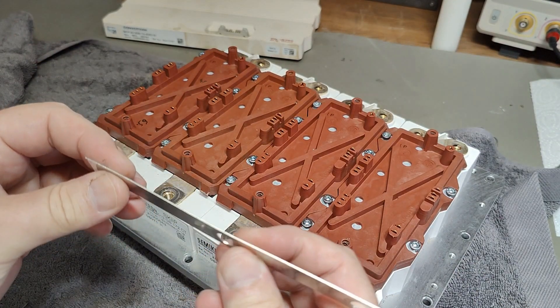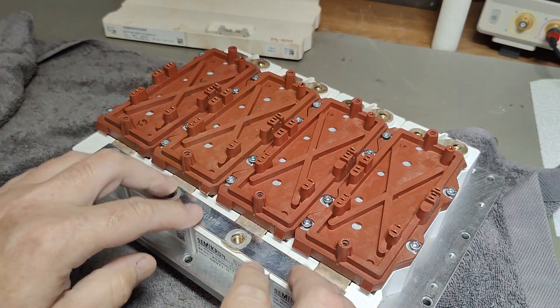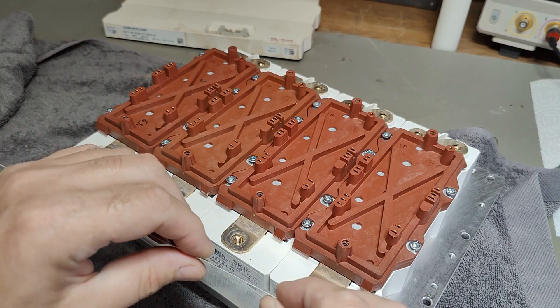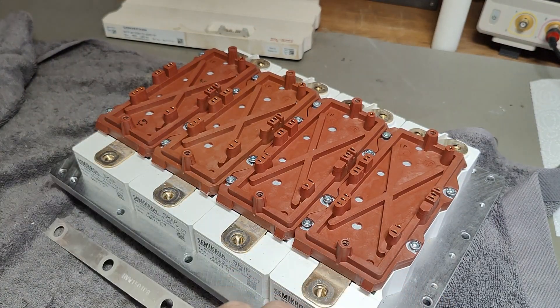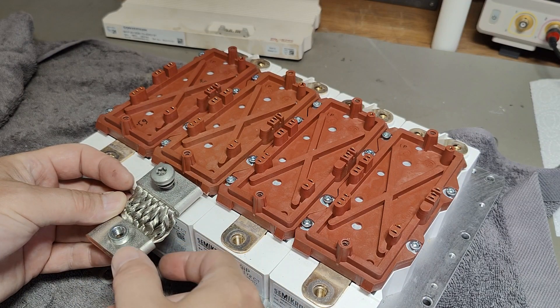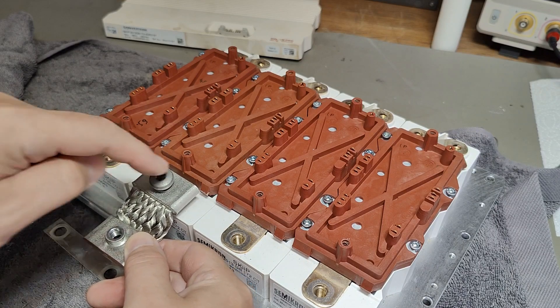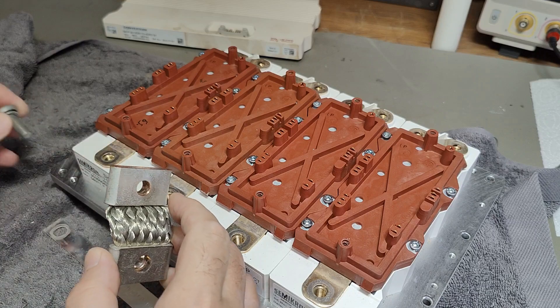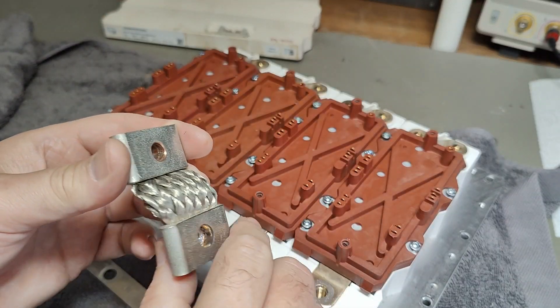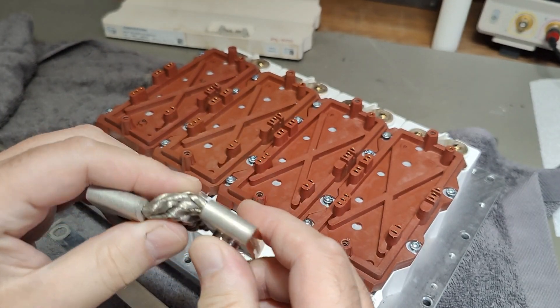So that is a thin, thin, flimsy parallel connection — this is probably only for testing or very, very low current. I believe this goes down to a mega-thick output copper bar here. So this is where all the main current flows, and since this is rated 2000 amps for all four in parallel, we will have 500 amps going through each one.